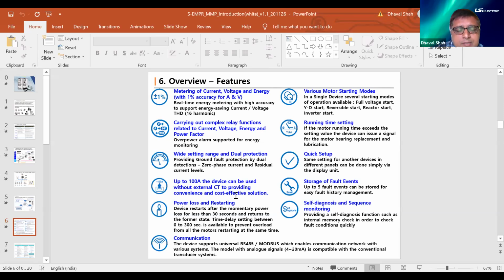And you get the advanced features. So power loss and restarting is there. When a device fails and it restarts, you can have a delay of 30 seconds or something; you can set up to 300 seconds. Communication is there in RS485, and you also have the analog module output, which is 4 to 20, wherein you can configure it as per your need.